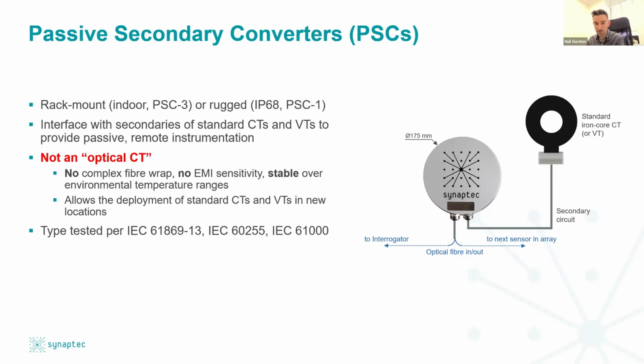You can actually think of this system of interrogators and PSCs together as like a very, very large merging unit that operates over very large geographical areas, because we're digitizing the secondary of a CT and making that measurement available in a substation, which could be tens of kilometers away. Now, in terms of installation of these devices, it's very, very straightforward and quick. So a CT, for example, can be deployed at a cable sealing end. Say you want to do a mixed circuit protection application, like Sol will come to in a moment. There you want to install your CT around the insulated cable, mount your PSC nearby, and make the electrical connection to the CT. And then the optical fiber connects in series through all of the sensors in the array.